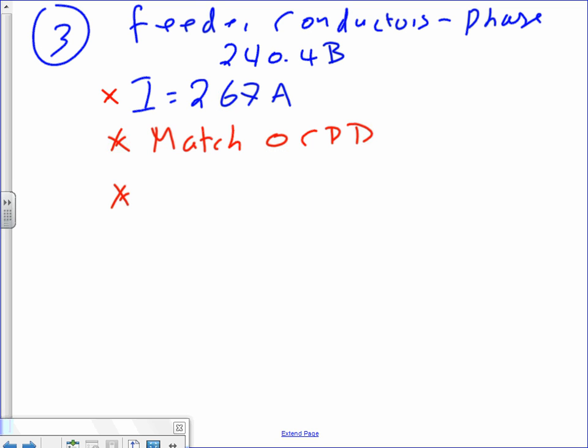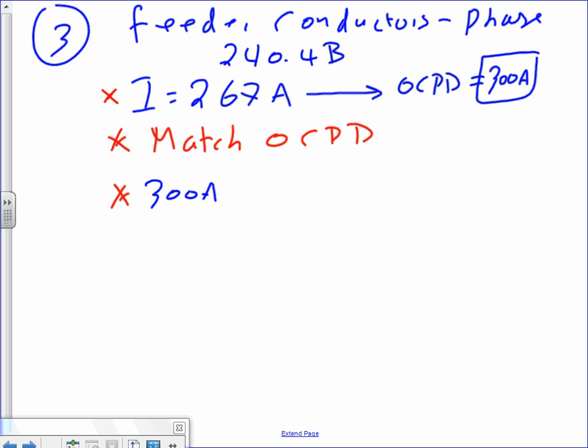Now, feeder overcurrent protection device, 267 amps. Now, the way I typically do it, guys, my overcurrent protection device. What was the overcurrent protection device for the panel? 300 amp, right? We just did that. Match the overcurrent protection device. When you size the conductor for a panel, here's the amp that you need to size for. But instead of using the amps that you calculated, always match the conductor to the overcurrent protection device. That's kind of the engineering way of doing it. Then I have 300. Everybody knows where the 300 came from?